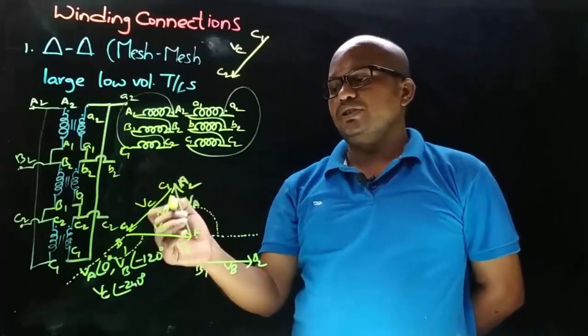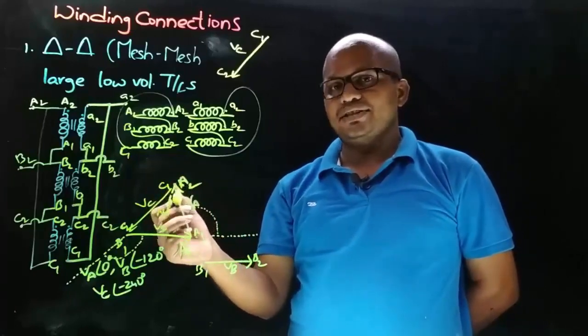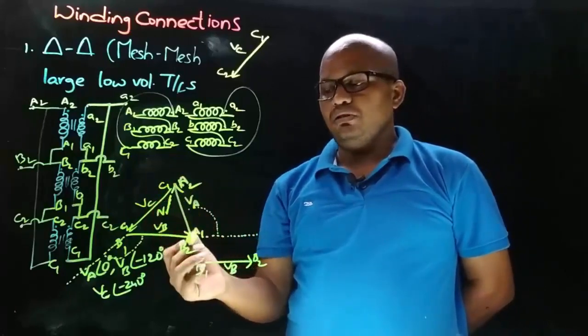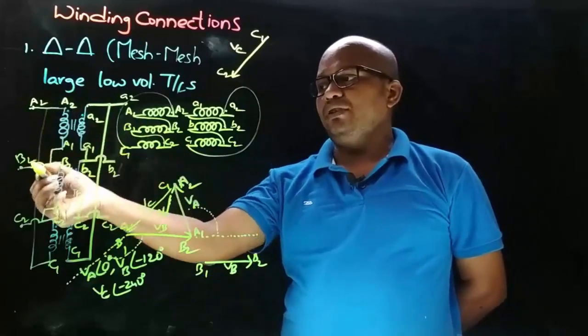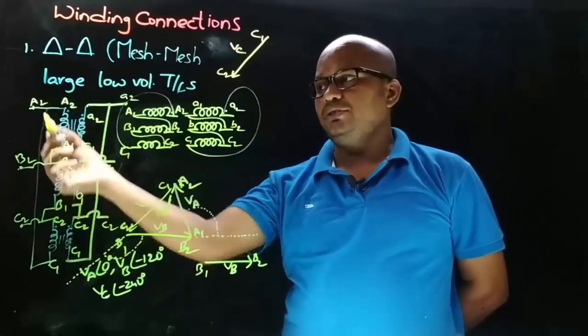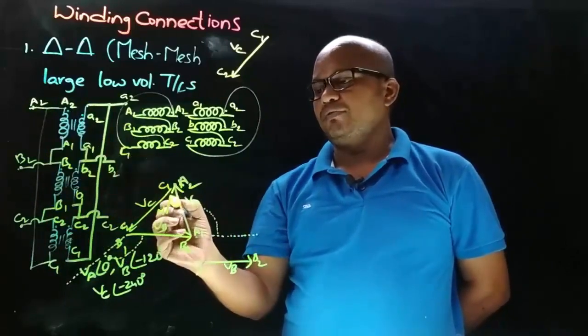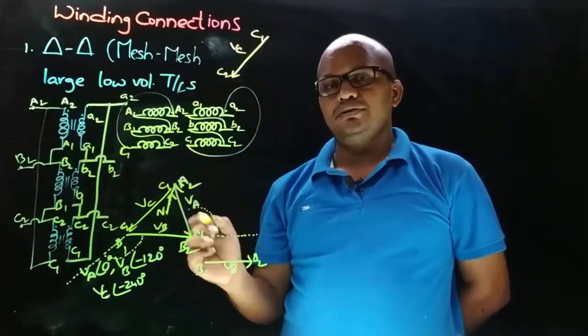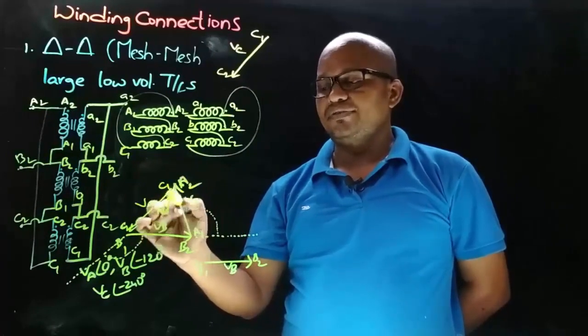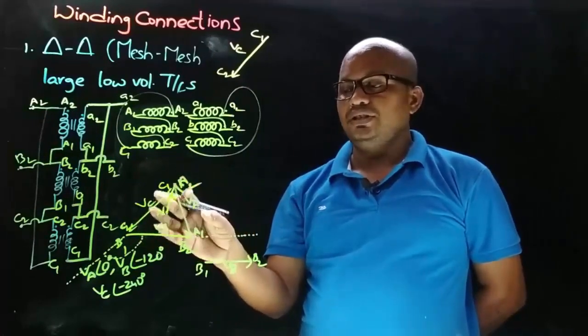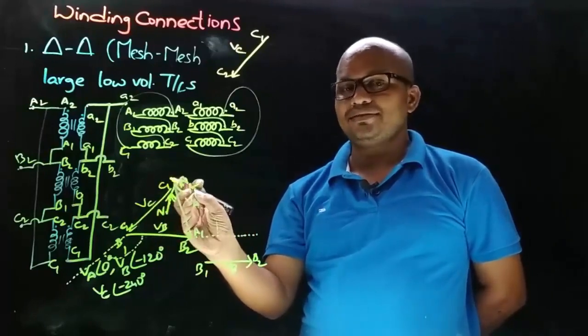So if you have a doubt whether to take the reference phasor from A2 or from A1, then just observe the winding connections we took from. So here we took from A2, means reference phasor must be always pointed towards the connection we took from. So this is the reference phasor. So this is how the delta connection phasor diagram is drawn.